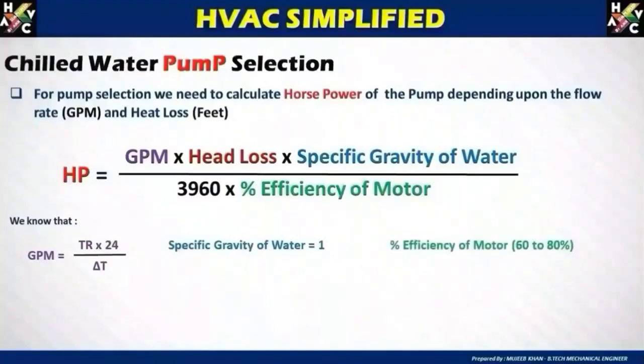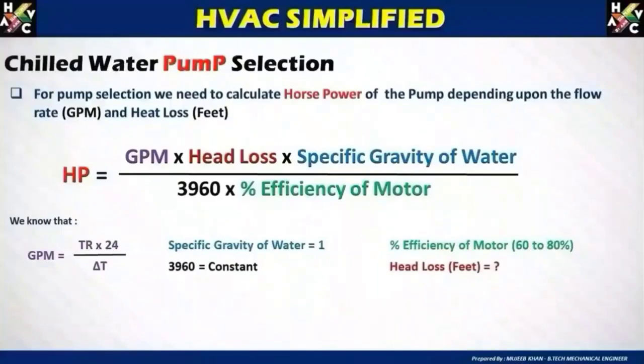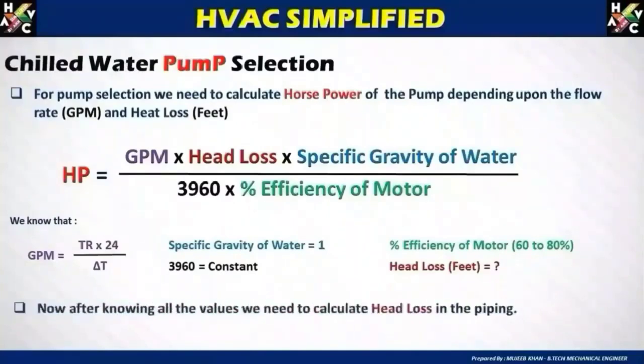The specific gravity of water is 1. The efficiency of the motor is usually taken between 60 to 80 percent. The constant 3960 is a fixed parameter. Head loss is calculated in feet, meters, or KPa. I have made a separate pump head calculation video which I will add in the link description where you can check it in detail.